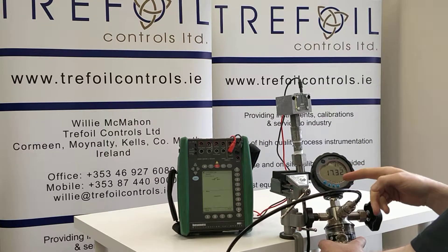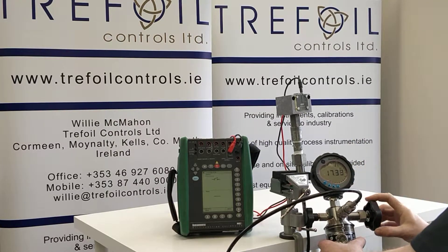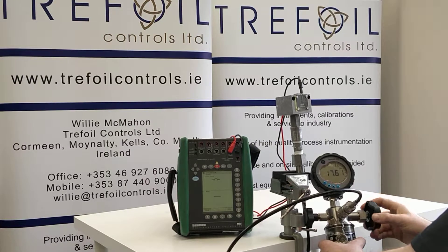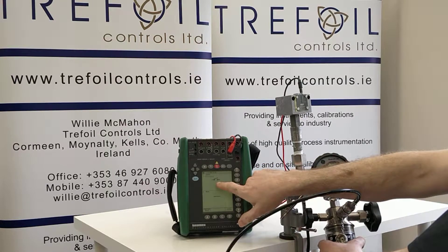So here we are now. You can see 17.3 bar — rather than starting from zero, I am going to bring this all the way up to just above 18.3 bar. You will see the switch. Our switch at the minute — our attention over here — is open.